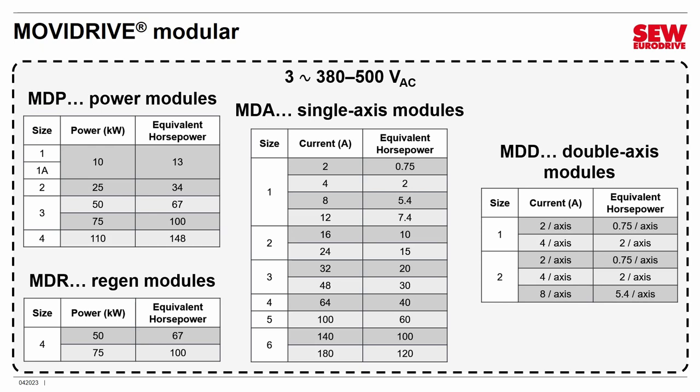Double-axis modules are a little more limited, but remember they handle two motors each — they handle between 2 and 8 amperes, about three-quarters of a horsepower up to 5.4. There's some overlap in size 1 and size 2: size 1 modules are smaller and meant for applications where space is at a premium, but they don't have expansion slots, so you can't add expansion cards. If you need those slots and don't care about space, size 2 is the choice. All these numbers are based on 4 kilohertz pulse width modulation.